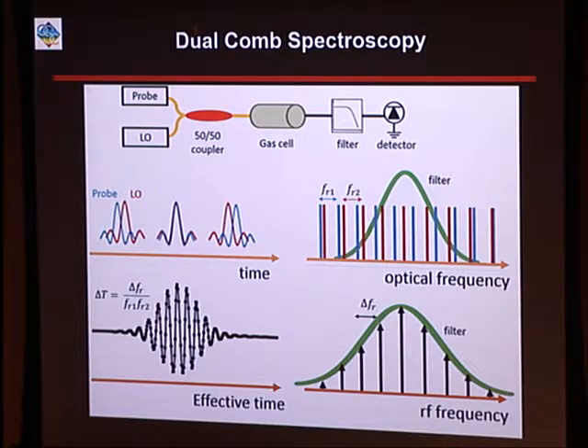In the dual-comb technique, you have two mode-locked lasers, the local oscillator and the probe. These lasers emit two femtosecond pulse trains, but they have slightly different repetition rates, right? So in time, if you look at the pulses, one pulse would run across the other, right? So you basically have a system that does the delay scan automatically without any moving parts, right? When you look at this system, you can get an interferogram that looks like this. If you Fourier transform this interferogram, you can get the spectrum as well. Depending on the difference in the repetition rate, which is around a kilohertz or so, every 1 millisecond you get a spectrum coming out. So it's very fast. So if you look at the frequency domain, right?